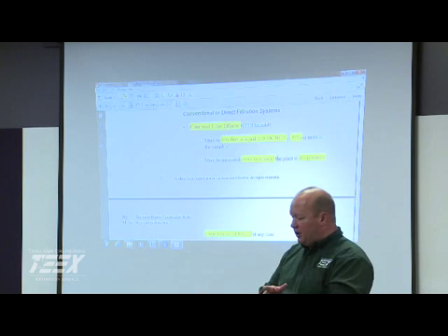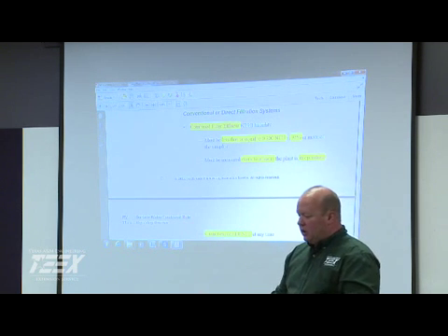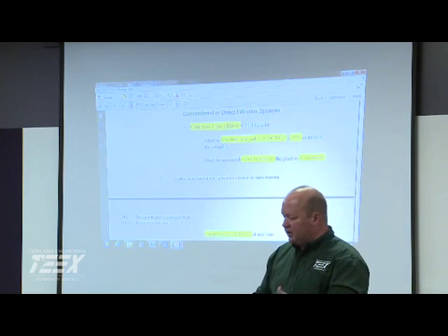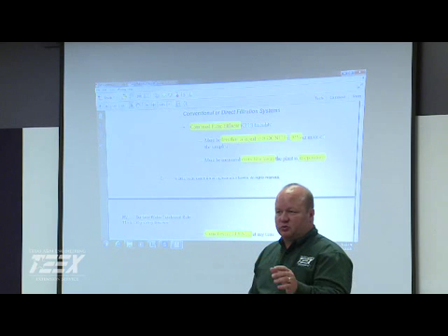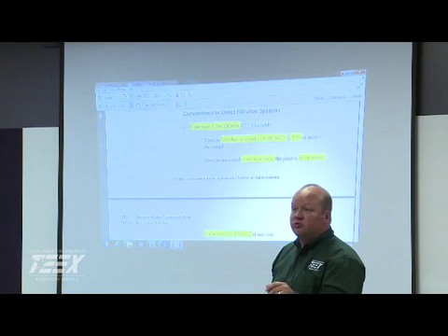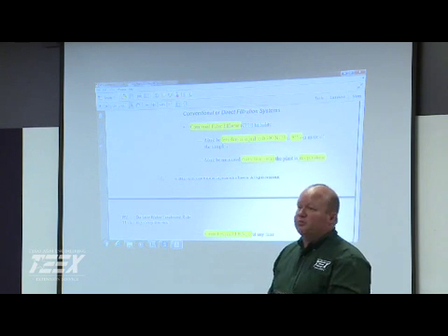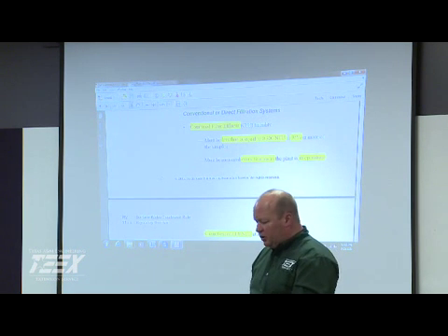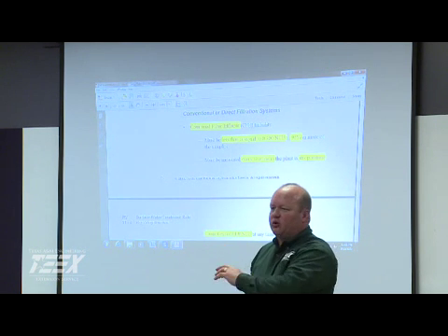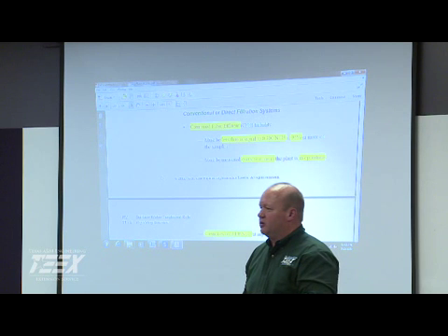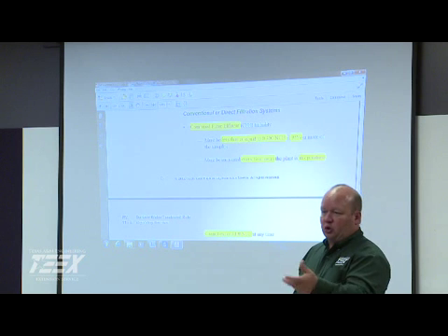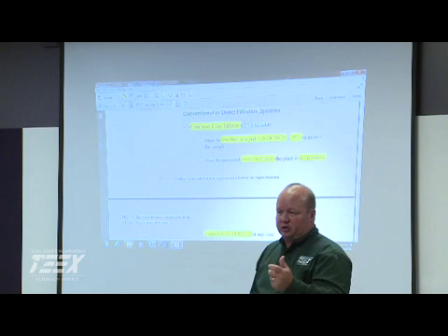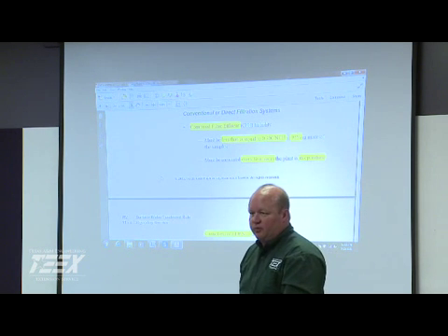So we're looking at our combined, and then we're looking at our individual also. Combined filter, got to be less than 0.3 NTUs 95% of the time. Y'all have online continuous monitoring for your filters? For your filters? With the turbidity? Yes, ma'am. And then you have one for combined also? I know a lot of people are getting into particle counters now. We're working on that. We've got part of it. We're still waiting on another part to get here. It's ordered. So are you pulling samples and running them through a benchtop?